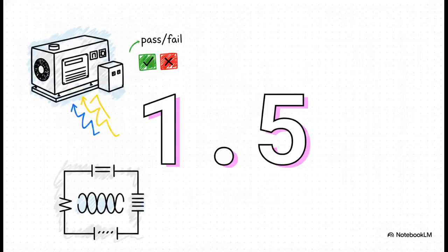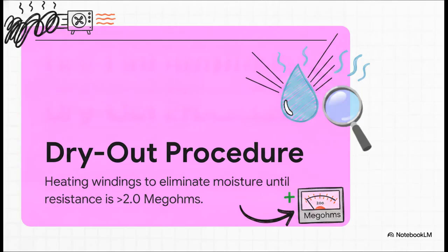So let's put your knowledge to the test. Imagine you hook up your diagnostic tools. You run a Megger test on a generator that's been sitting cold for a month, and your tool reads exactly 1.5 megohms of resistance. You have to ask yourself, does this reading pass or does it fail? Well, if you guessed fail, you're right. A reading of 1.5 megohms is a strict, undeniable failure.